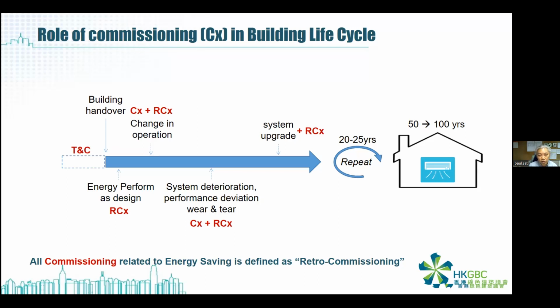And when the building is still in ongoing operation, equipment or systems may deteriorate, and the performance will deviate from the design. Wear and tear may also happen. At this moment, we also need to do commissioning and retro-commissioning in order to ensure the building operates in good condition and at energy efficient conditions. Finally, the equipment has a lifetime and will fail, and then we need to upgrade or replace it. So here we also need to do retrofit, and after the retrofit we need to do retro-commissioning to make sure that the new system operates as well as the design. This kind of cycle repeats in Hong Kong around every 20 to 25 years. So when the building is 100 years old, it takes around 3 to 4 times.